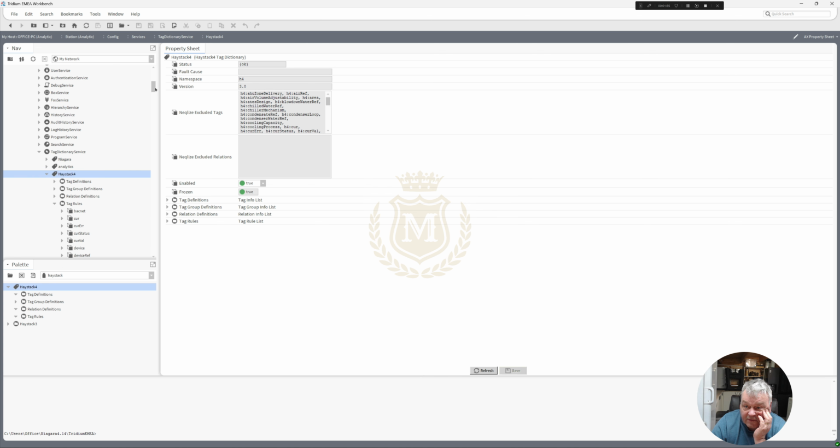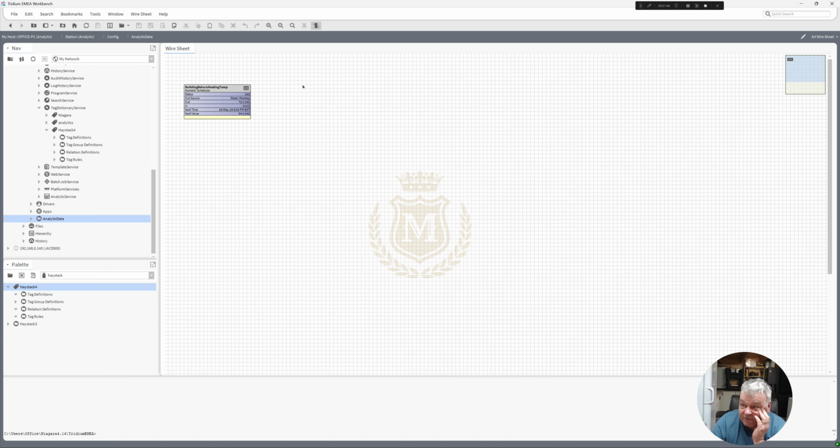If I go back into our analytic folder, views wiresheet, and make a new numeric writable and call it building return heating, and we've got temp already for the scheduler, so I'm going to put an underscore temp because you can't have the exact words. It would put a 1 at the end if you had the exact words.